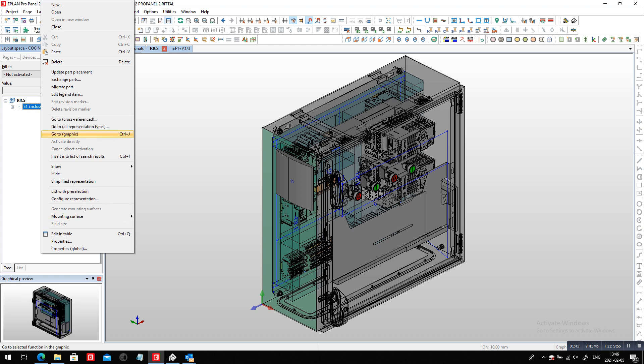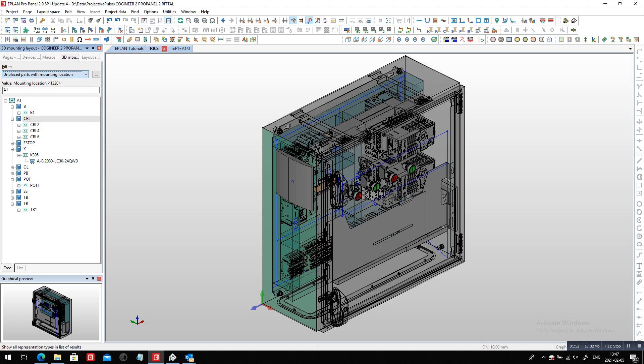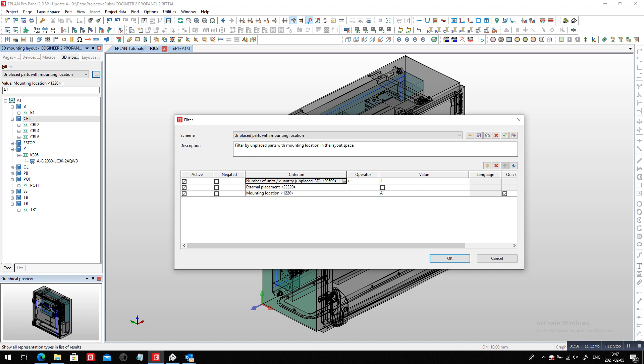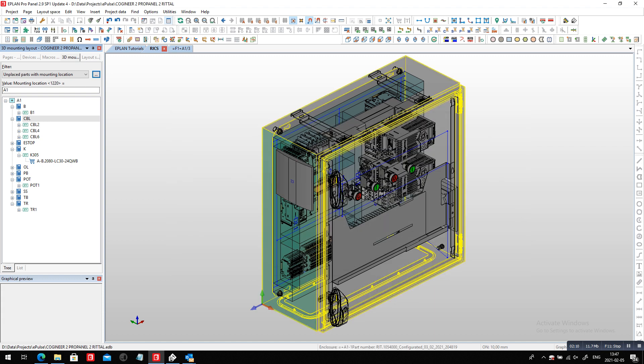And now I will work on my panel. So the idea is, of course, how do I, when you go here inside your panel and you decide to fill out the panel with all the components that should be mounted, how do you ensure that all your devices have been mounted? Well, here I have an unplaced parts with mounting location as a filter. And I can see here, this filter was simply created based on a number of units of unplaced components. It has to be greater or equal than one. External placement, of course, not activated. And mounting location equals A1. So I can see all the devices that are assigned with a part number that show up here.